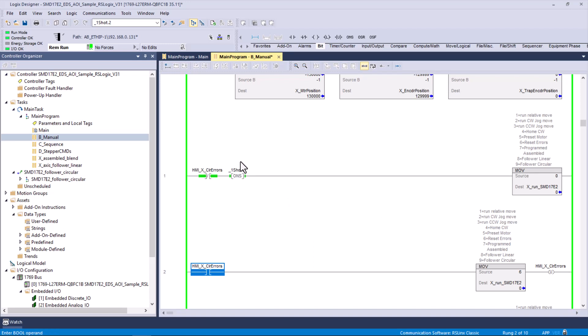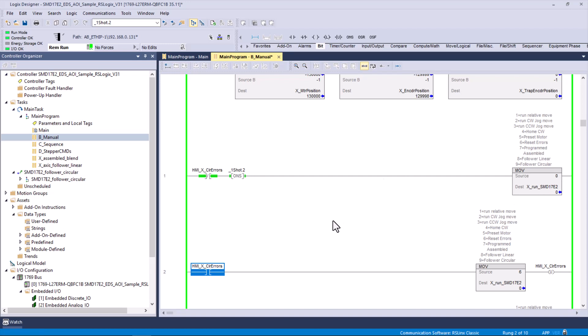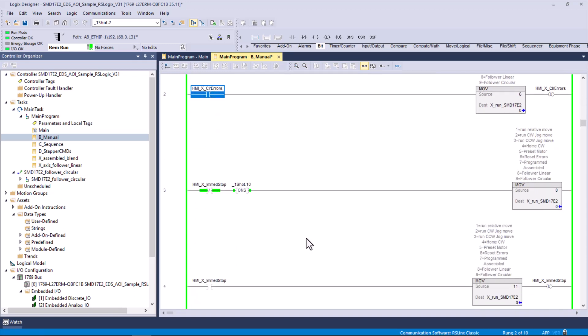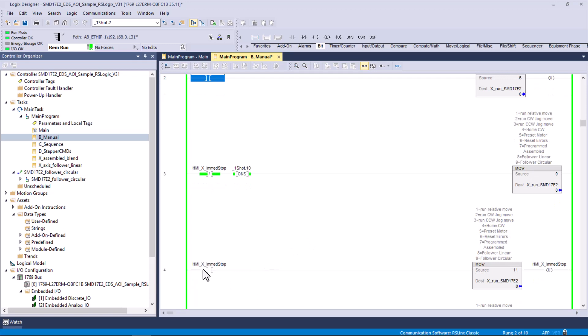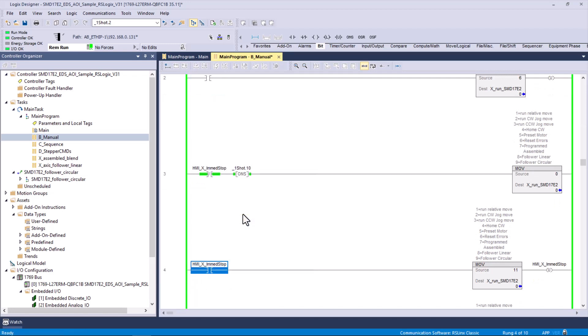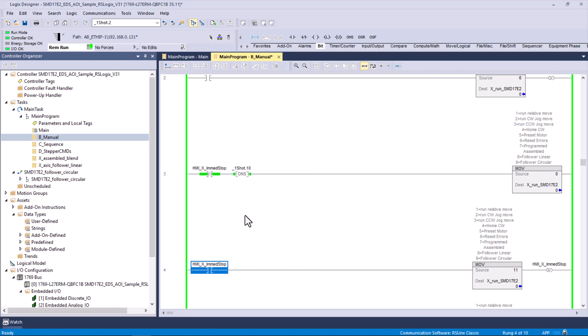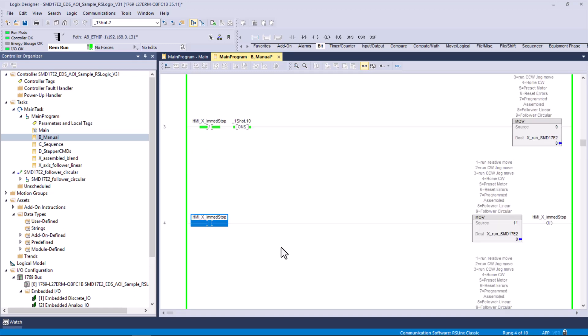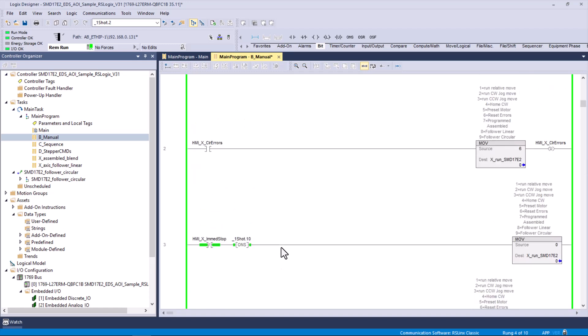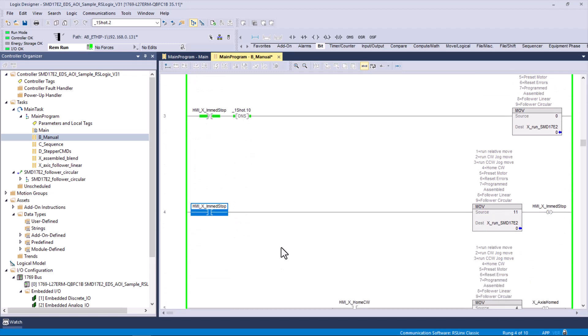We can't not have this one shot because if you're not pushing that button, it's putting a zero in there all the time. We did the exact same thing for immediate stop. It's not an emergency stop, but just an immediate stop. You'll never see the state change. If you watch this logic and I right click, toggle bit, if you see an 11 here or if you see this bit on, it's just an odd catch in the scan times of my computer, my monitor, the video card. But you're not going to see it change, but it does.